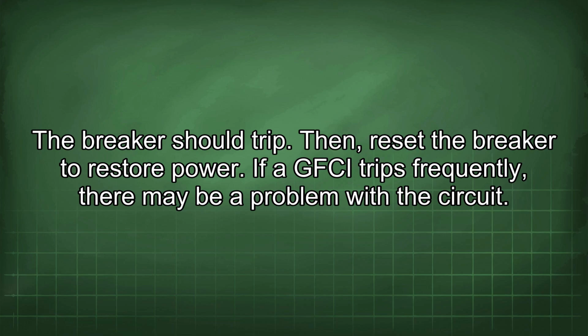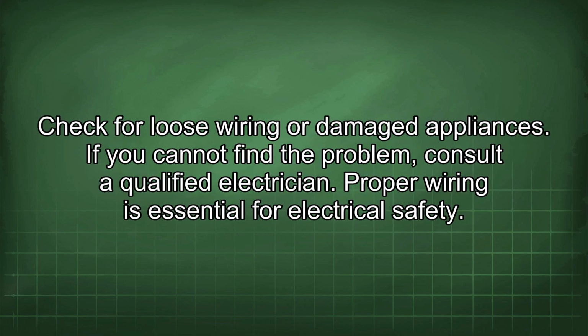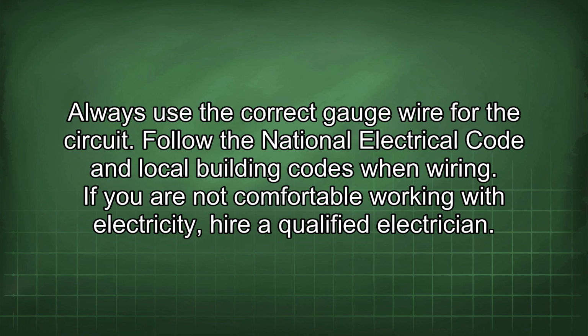If a GFCI trips frequently, there may be a problem with the circuit. Check for loose wiring or damaged appliances. If you cannot find the problem, consult a qualified electrician. Proper wiring is essential for electrical safety. Always use the correct gauge wire for the circuit. Follow the National Electrical Code and local building codes when wiring. If you are not comfortable working with electricity, hire a qualified electrician.